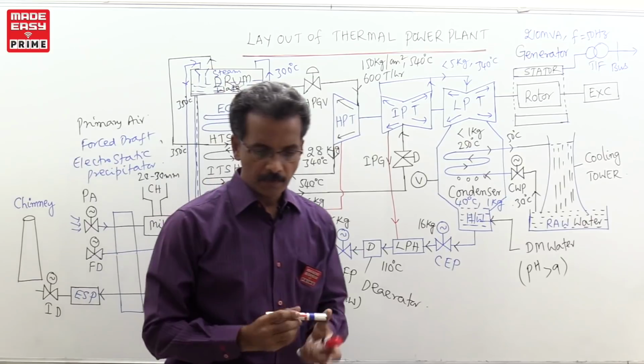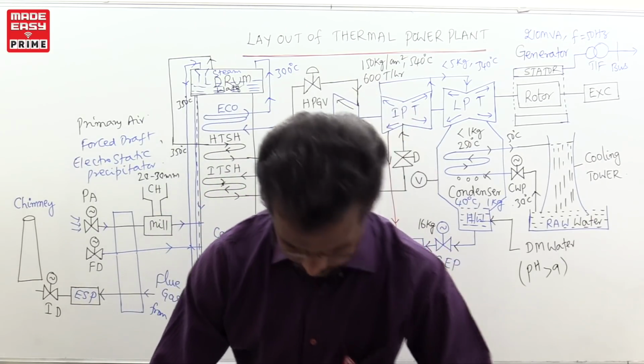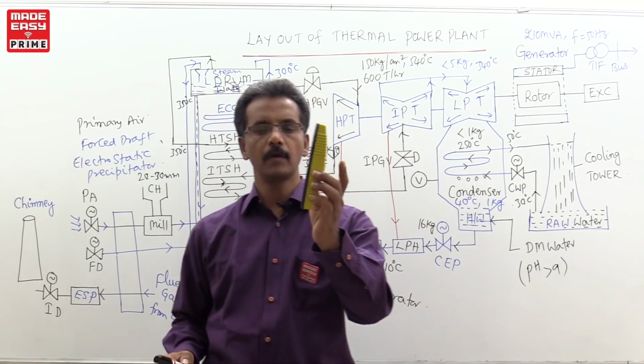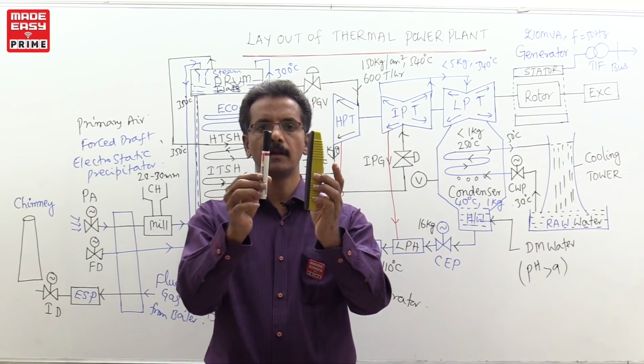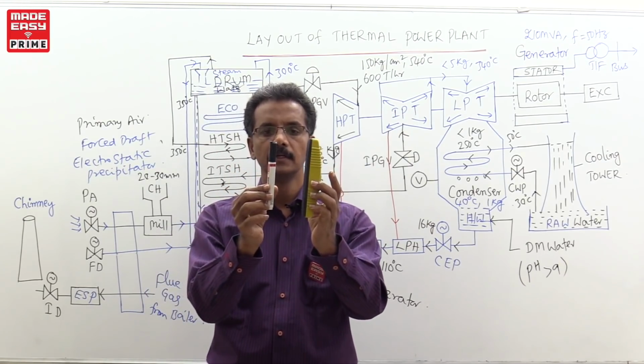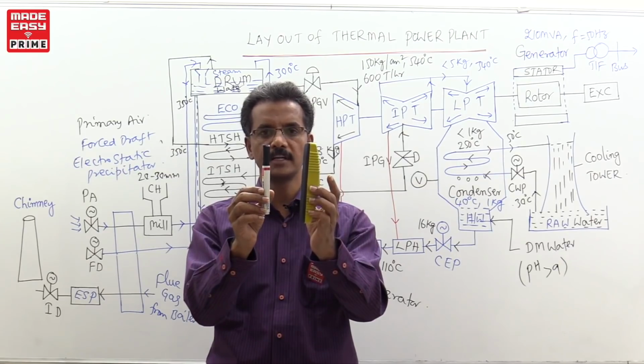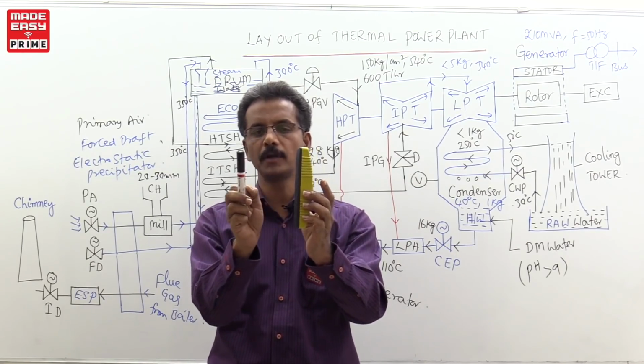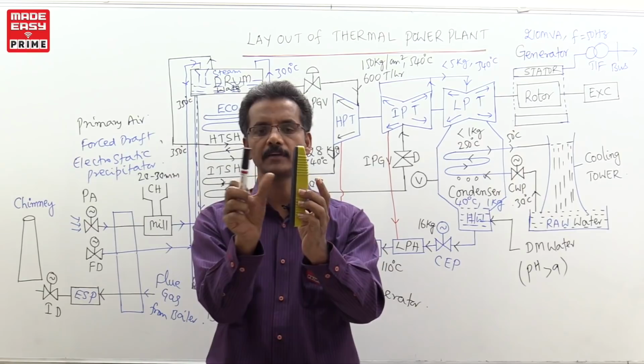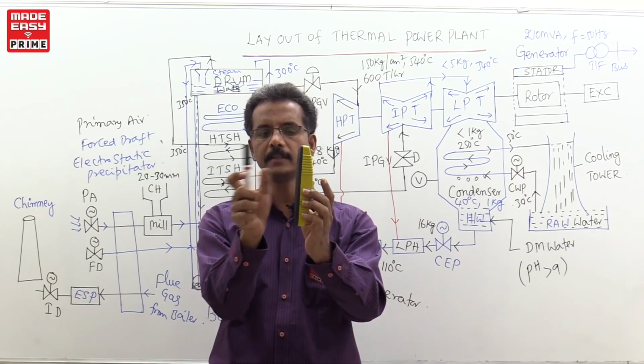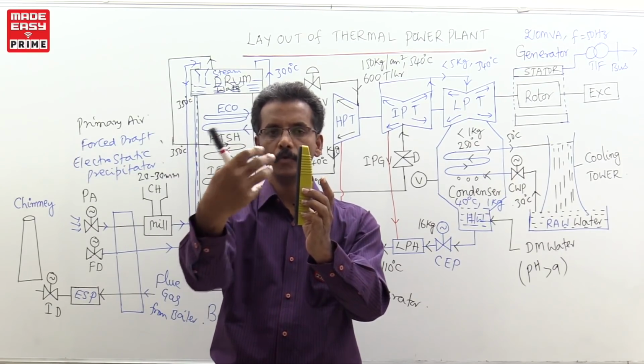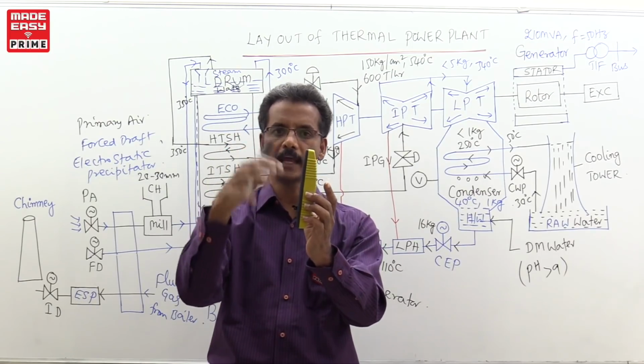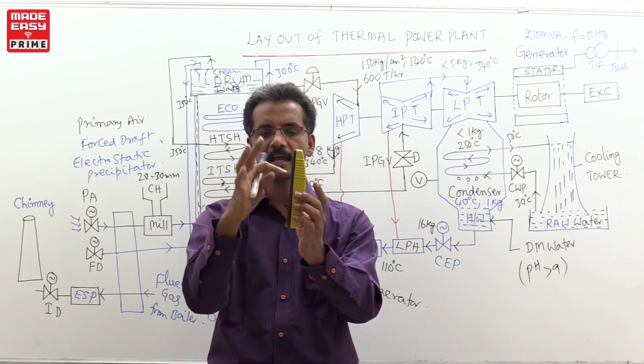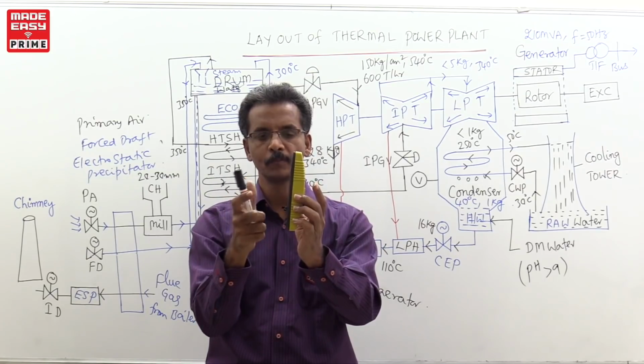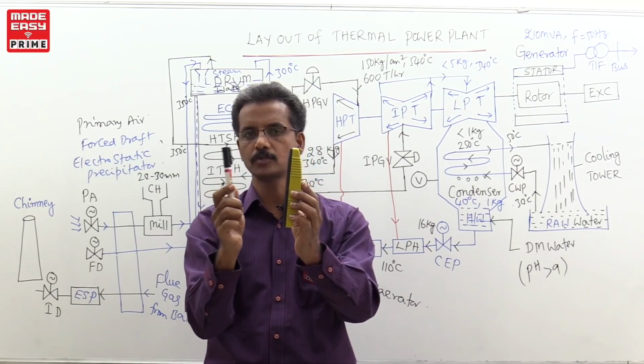It works on the principle of an electrical field. Imagine this is one plate, and this is another plate or simple wire. In between, some potential is applied. So what will happen? From the positive plate to the negative plate, an electrical field is generated. Now, in between this gap, I am sending the flue gas. That flue gas contains ash particles, and these ash particles have both positive and negative charge carriers.